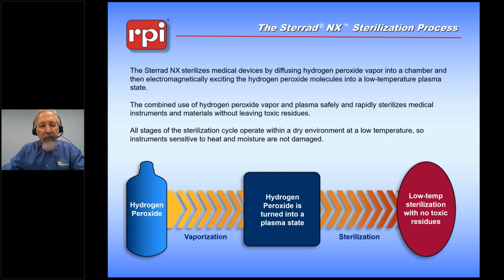It uses a solution of hydrogen peroxide to sterilize the material within the chamber. This hydrogen peroxide is delivered as a 59% solution. It's concentrated down to 90%. Then it's injected into the chamber with all the material, and then it's turned into a plasma. And the plasma will take the 90% hydrogen peroxide and turn it into water and free radical oxygen, which will actually do the sterilization process.